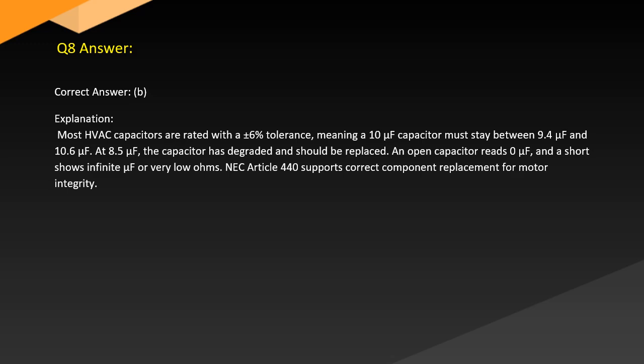Answer. Correct answer: B. Explanation: Most HVAC capacitors are rated with a plus or minus 6% tolerance, meaning a 10 µF capacitor must stay between 9.4 µF and 10.6 µF. At 8.5 µF, the capacitor has degraded and should be replaced. An open capacitor reads 0 µF, and a short shows infinite µF or very low ohms. NEC Article 440 supports correct component replacement for integrity.